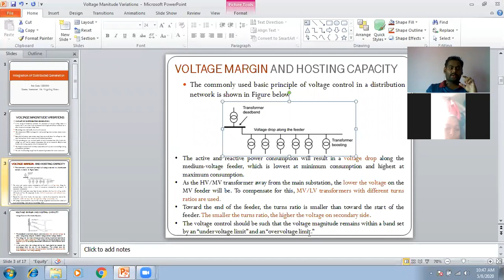So the voltage control in the distribution system. This is the curve we can see here. The first thing you can see is the over voltage limit, the upper limit, and this is the under voltage limit. This is the voltage magnitude, and as the load decreases or increases, this is a voltage drop. This curve is the voltage drop at maximum load, and this curve is the voltage drop whenever the minimum load takes place. For a maximum load, the maximum voltage drop takes place. For a minimum load, the voltage drop will be less.